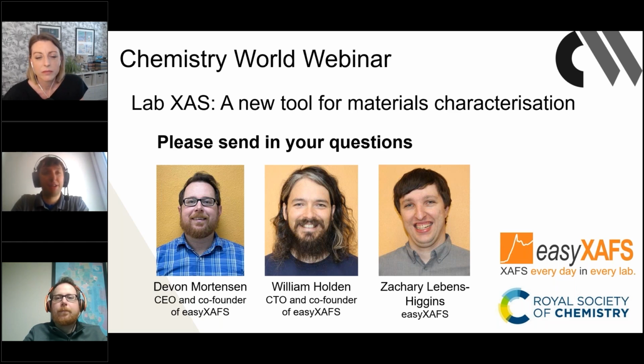Yeah. So for our instrument as well, you would have to do a calibration. It usually is done before a whole set of measurements starts or at the end, and it's usually a very short process, in order to reference to a metal sample. We have very high stability, so that metal reference can be used for all subsequent measurements on the same element. And when you switch elements, you would do a new calibration. So rather than at a synchrotron where you're doing a calibration with every single sample, you're basically doing this one calibration, and then that will hold for all subsequent samples. Right, so that's done at the start of a run, and then you only do that once? Yeah, basically when you're switching crystals or when you're switching elements, you'll do it once at the start of that element set.